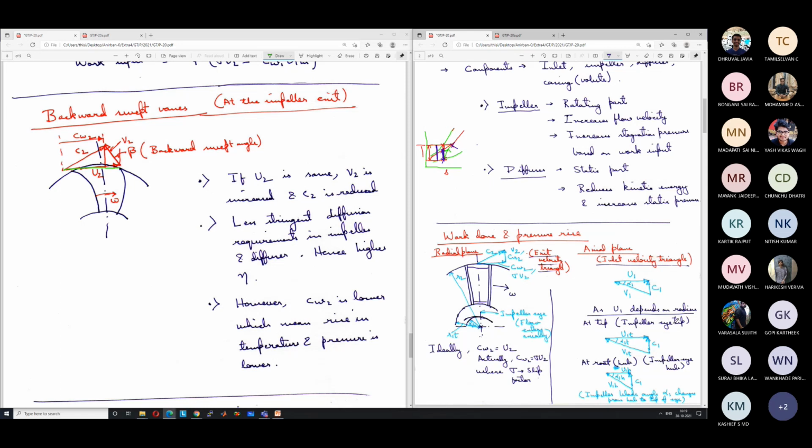As a result, because of very large centrifugal stresses, the blades, if they are bent like this, tend to straighten out over a long period of operation. Ultimately they have the tendency to become like this.